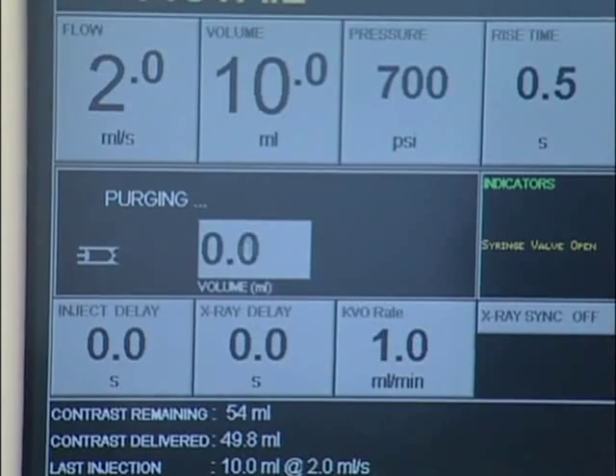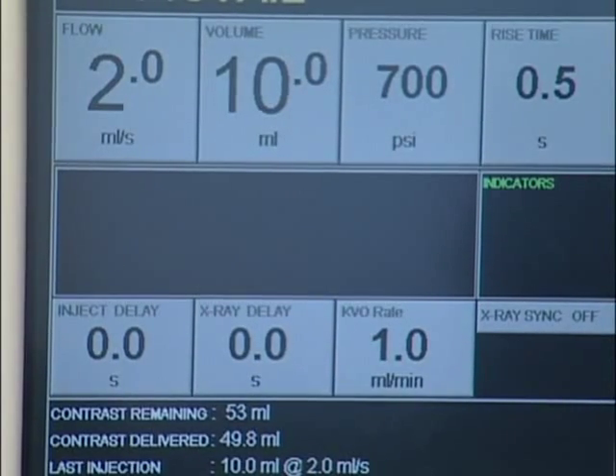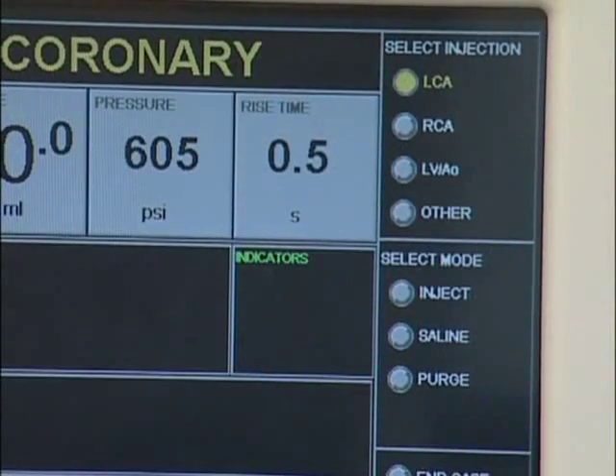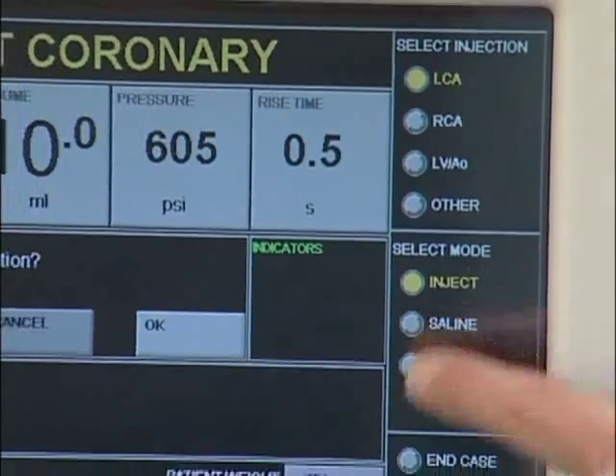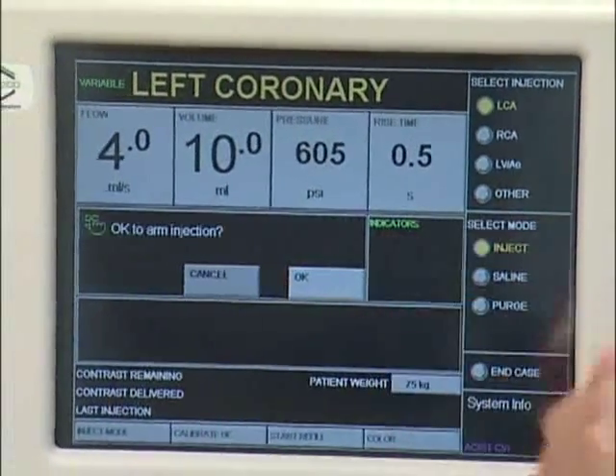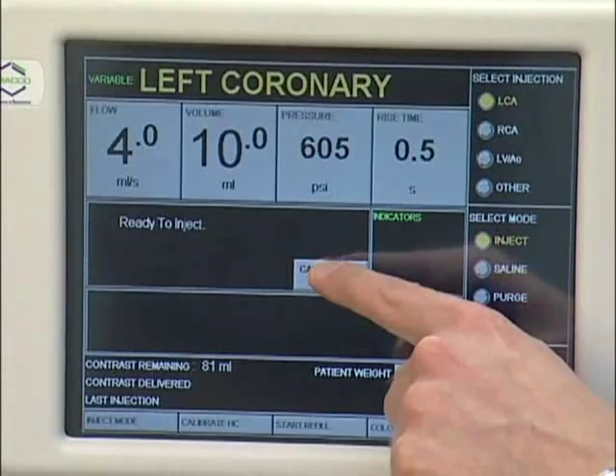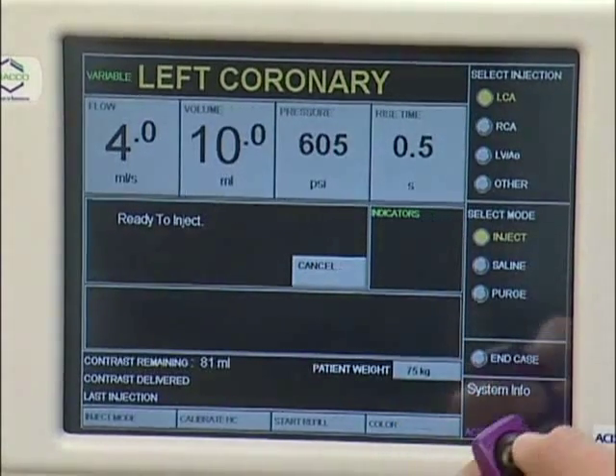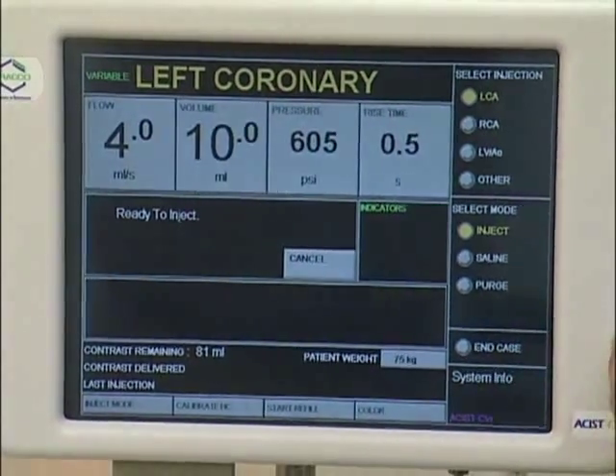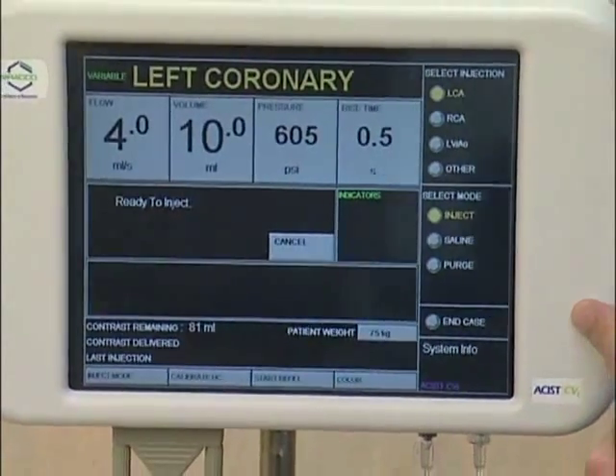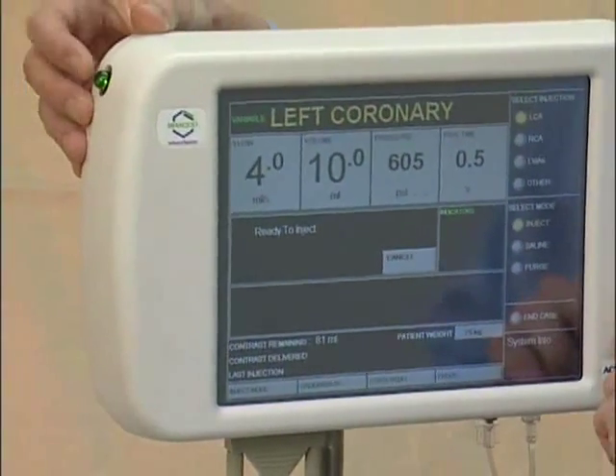The stop refill button is pressed and you'll see the system automatically purged. To arm the system for injection, we'll press inject. The system asks you, is it okay to arm the injection? And if you press OK, the system is now ready to inject. You're also informed of that readiness by the armed light on the side of the control panel, which would illuminate.